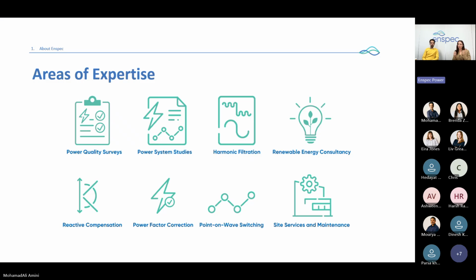We help in one of three main ways. We have a very developed and technically astute consultancy department who focus on power system studies and simulations to show whether or not a site does in fact meet grid code requirements. If they do, we submit our studies with an application in order to get the grid connection agreement. If they don't, we can design, manufacture, and commission mitigating solutions, things like harmonic filtration, reactive compensation, power factor correction, and point-on-wave switching.